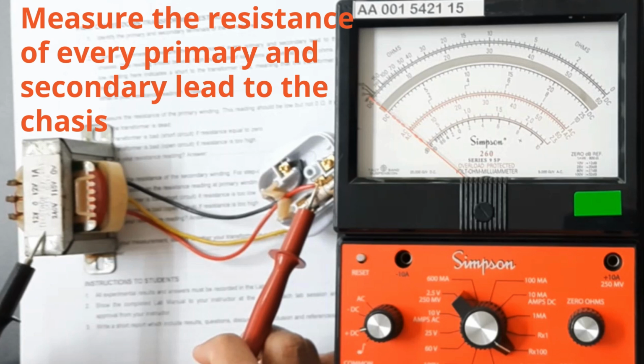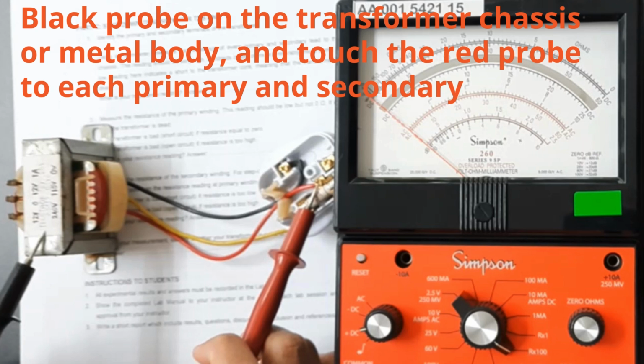Measuring resistance of primary and secondary leads to the chassis. First, place the black probe on the transformer chassis or metal body and touch the red probe to each primary and secondary terminal one at a time. The reading should be infinite, meaning the windings are insulated from the chassis. A low resistance reading would indicate a fault.